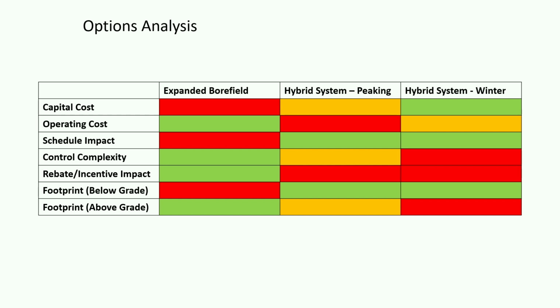The flip side of that is, in addition to capital cost, you have to consider your operational costs. It costs money to run one of these dry coolers or chillers. It does not cost that much money to have a borehole in the ground. Generally, when we look at this hybrid system run in the winter and we're running a dry cooler, it's more efficient. You probably don't have to have a compressor like you would with a chiller. You're just rejecting it straight into the cold air. You're going to use less electricity that way. Generally it will be a cheaper system to run.